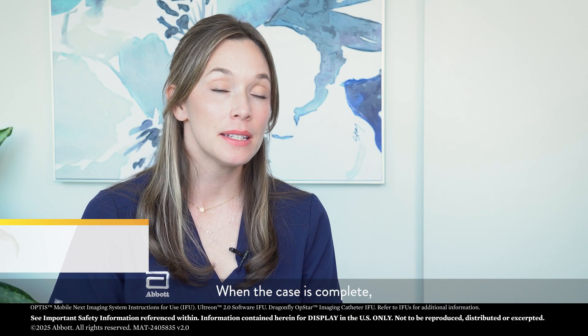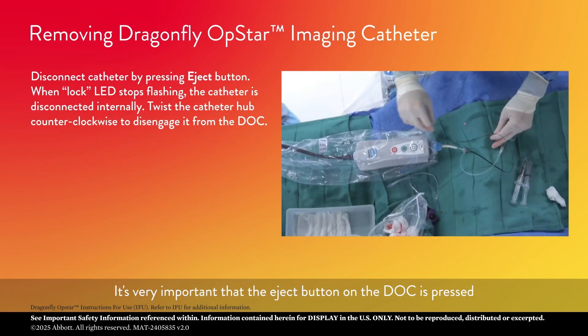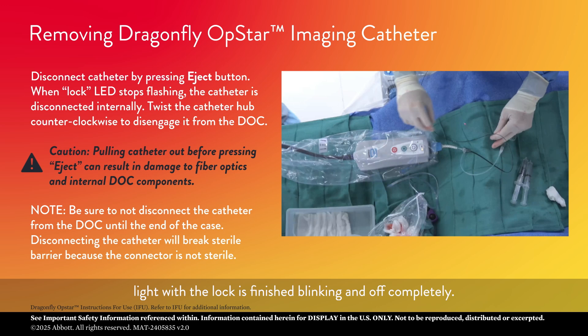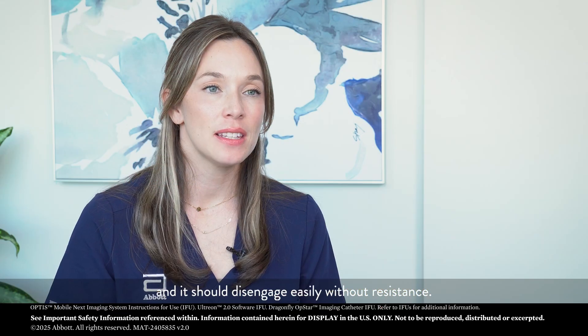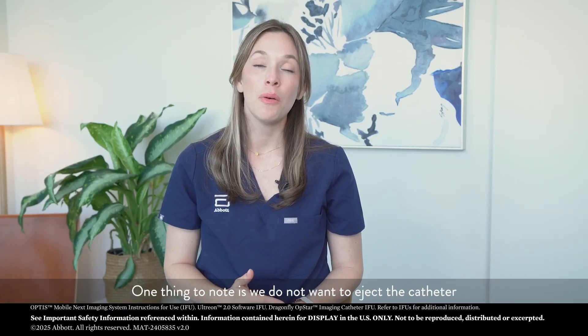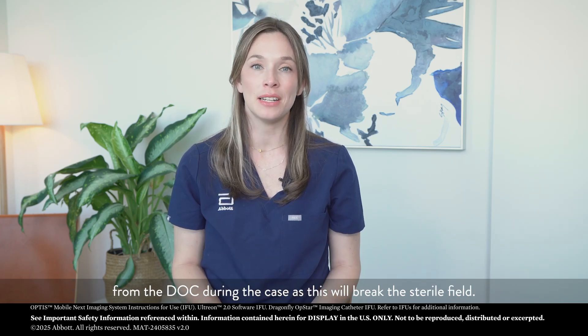When the case is complete, it will be time to eject the OCT catheter from the DOC. It's very important that the eject button on the DOC is pressed and the catheter is not removed until the indicator light with the lock is finished blinking and off completely. At that point, a gentle quarter turn can be given to the catheter and it should disengage easily without resistance. Note that we do not want to eject the catheter from the DOC during the case as this will break the sterile field.